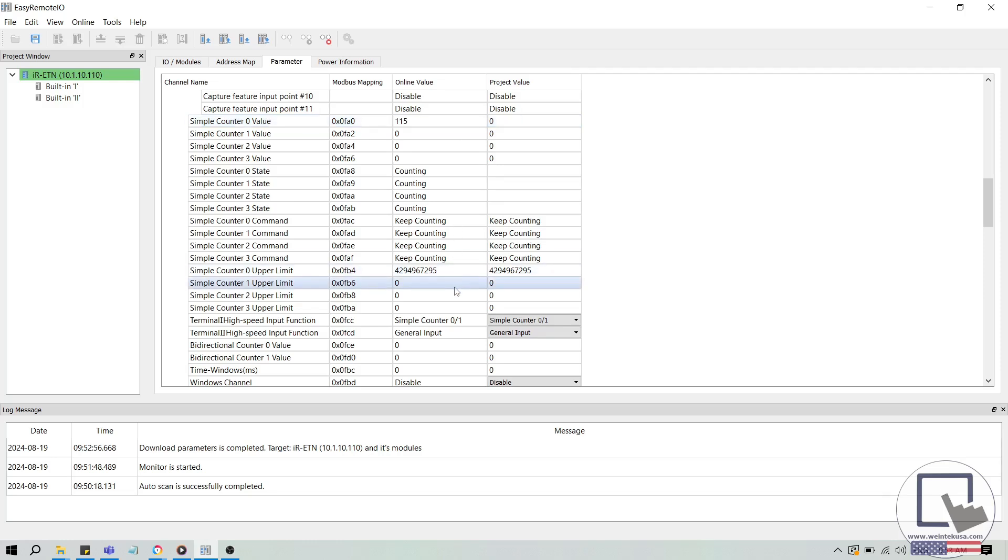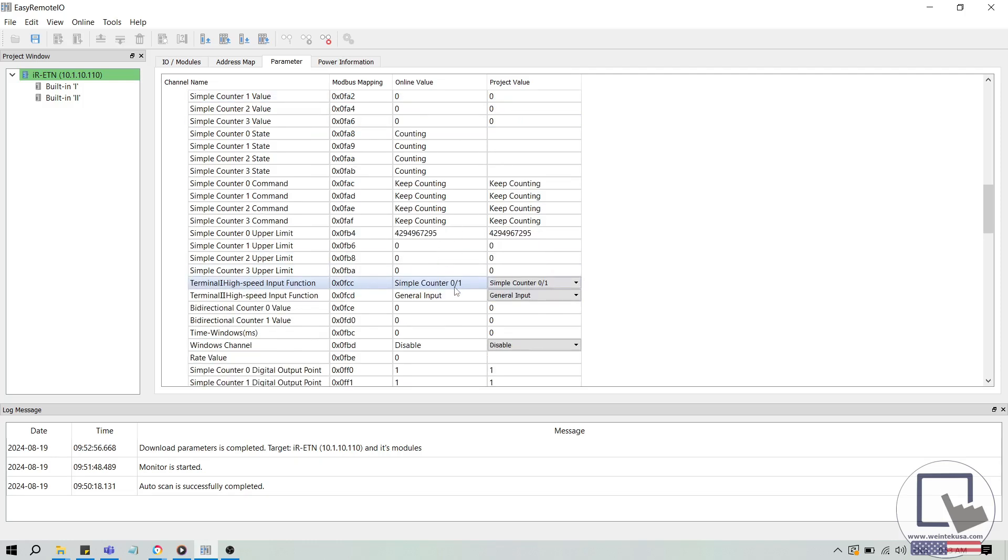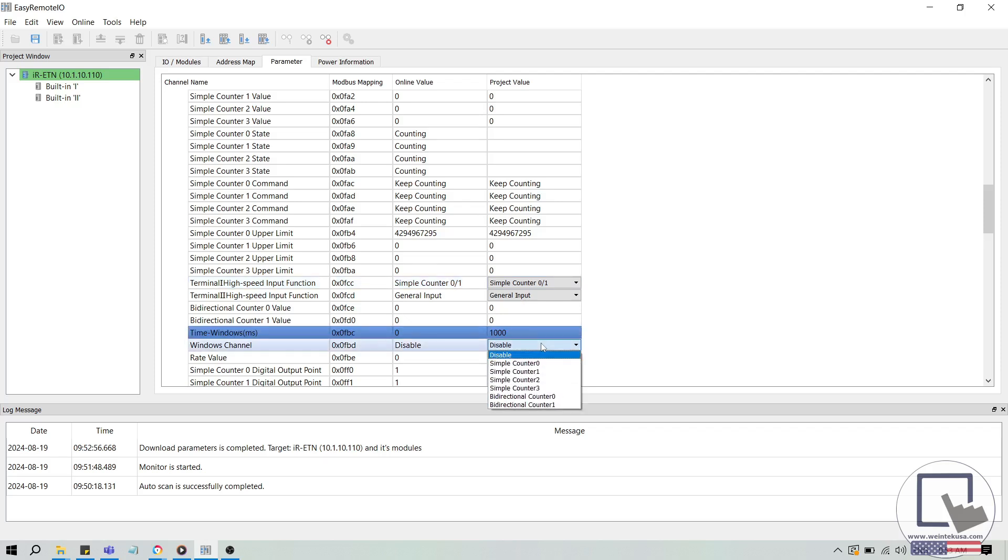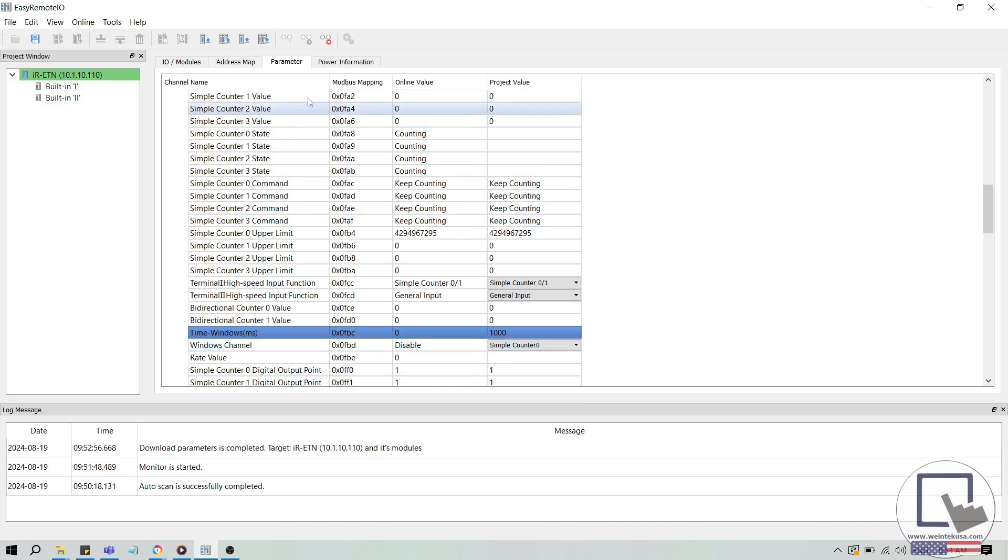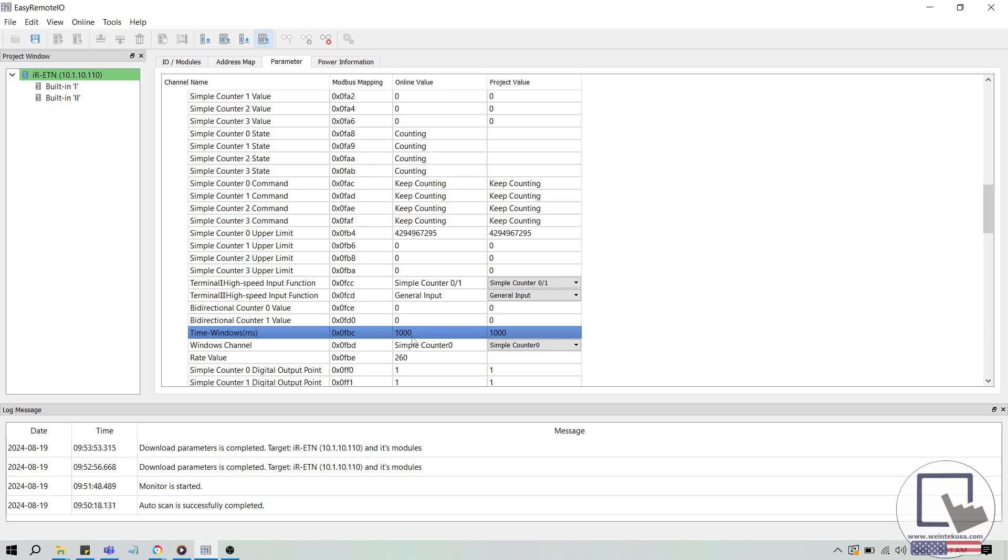Let's use rate calculation to determine the actual input frequency. I'll set the time windows parameter to 1000 ms, and the windows channel to simple counter 0, and download this change to our device. After a brief moment, the rate value now reflects the actual input frequency from our signal generator. I'd like to note that the time windows parameter is a scaling factor used in rate calculation, such that the input frequency is equivalent to the rate value divided by the time windows parameter in seconds.